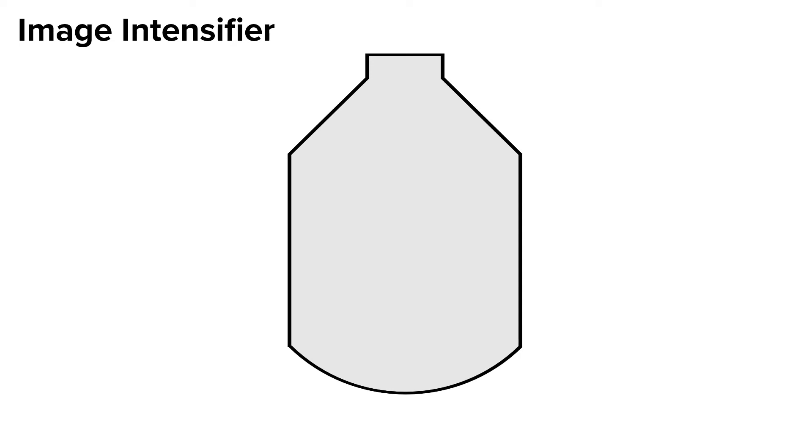There are six main components to the image intensifier. First, the whole image intensifier is about 9 inches long and is encased in glass. Within the glass, voltage can reach up to 25,000. Second, the input phosphor acts as a scintillation layer which converts x-rays into light.